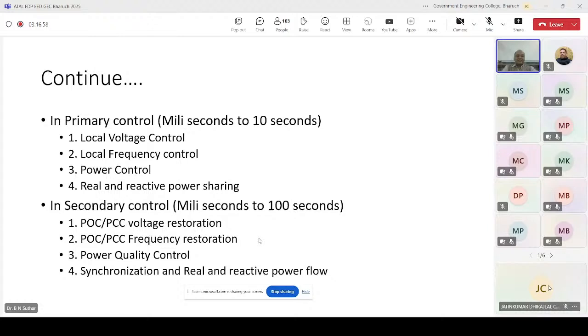Then the third one is power quality control. It has to control the quality of power - harmonics, real power, reactive power, power factor, everything. And the final one is synchronization and flow of real and reactive power from load to source, or from grid to microgrid. So these two controllers, primary and secondary, will have these kinds of functions.